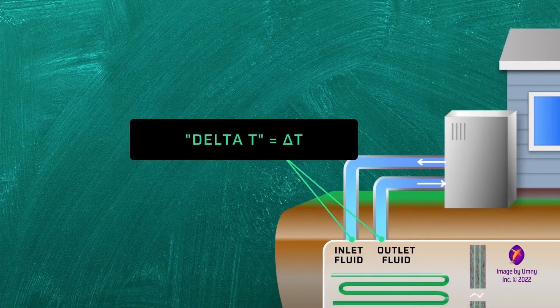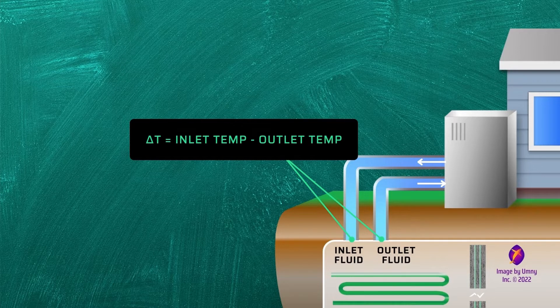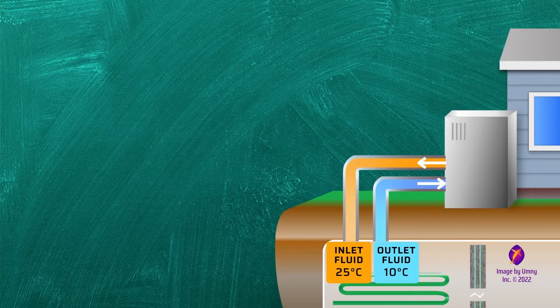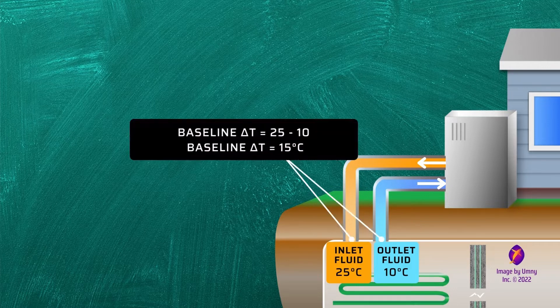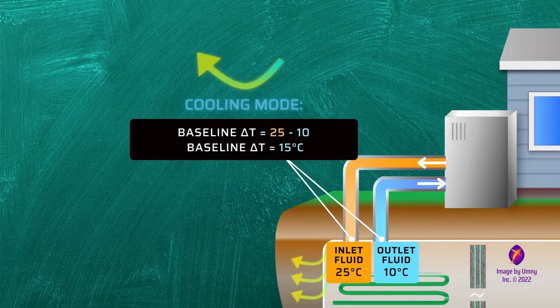A common term for this variable is delta T, and it is calculated as the inlet temperature value minus the outlet temperature value. We will call this the baseline delta T to refer to the original design value that we expect to see in our system. If the inlet fluid temperature is coming in warm at 25 degrees Celsius and exiting cool at 10 degrees Celsius, then our baseline delta T for this system is positive 15. This is because the equation for delta T is inlet temperature minus outlet temperature, not the other way around.